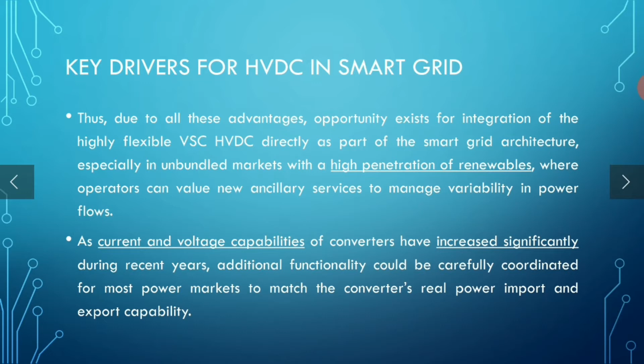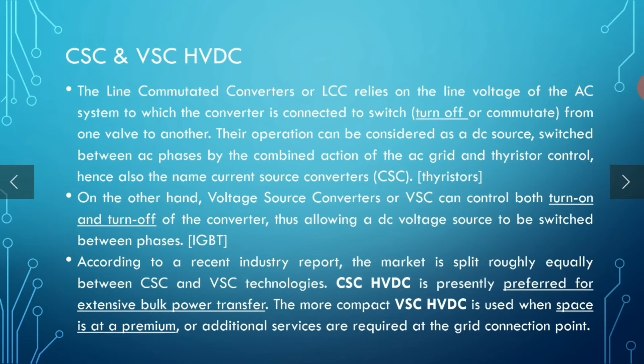In HVDC links, mainly two types of converters are employed. The current source converters, or line commutated converters, rely on the line voltage of the AC system to commutate. Their operation can be considered as a DC source switching between AC phases, hence the name current source converter. Here thyristors are used. In thyristor based converters, there are certain limitations. So, IGBT based converters are used, which are voltage source converters, in which both turn on and turn off can be controlled. Thus, DC voltage can be switched between two phases too. Generally, CSC based HVDC is preferred for extensive bulk power transfer, whereas VSC HVDC is used where the space is at a premium or additional services are required at the grid connection.